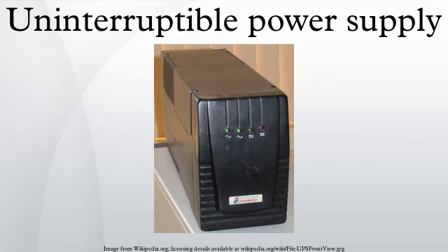Testing of strings of battery cells. Multi-kilowatt commercial UPS systems with large and easily accessible battery banks are capable of isolating and testing individual cells within a battery string, which consists of either combined cell battery units or individual chemical cells wired in series. Isolating a single cell and installing a jumper in place of it allows the one battery to be discharge tested, while the rest of the battery string remains charged and available to provide protection. It is also possible to measure the electrical characteristics of individual cells in a battery string, using intermediate sensor wires that are installed at every cell-to-cell junction, and monitored both individually and collectively.